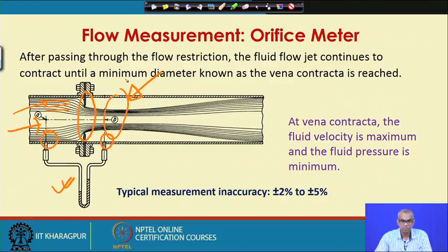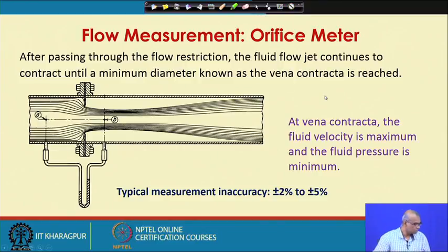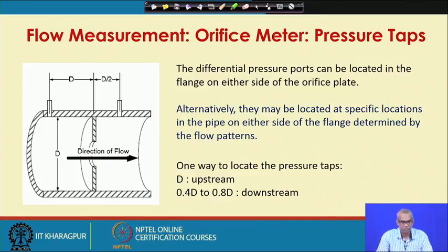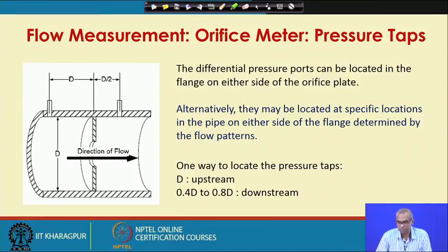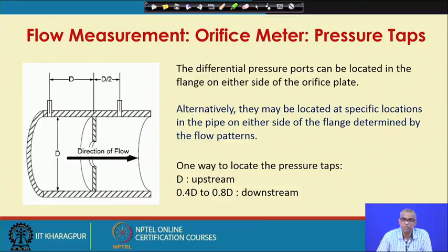The typical measurement inaccuracy of an orifice meter is generally ±2 percent, but sometimes it can go as high as ±5 percent. To measure the flow rate using an orifice meter, we have to measure pressure drop across the orifice plate. The differential pressure ports can be located in the flange on either side of the orifice plate. Alternatively, they may be located at specific positions in the pipe determined by flow patterns — for example, at the vena contracta.